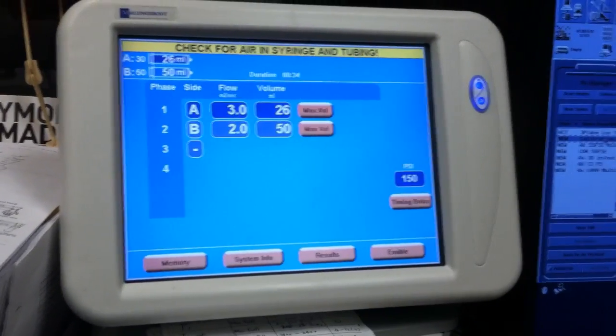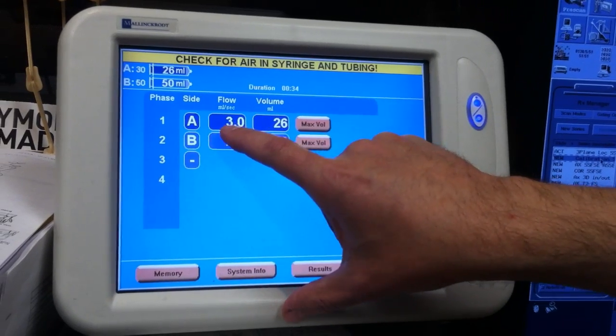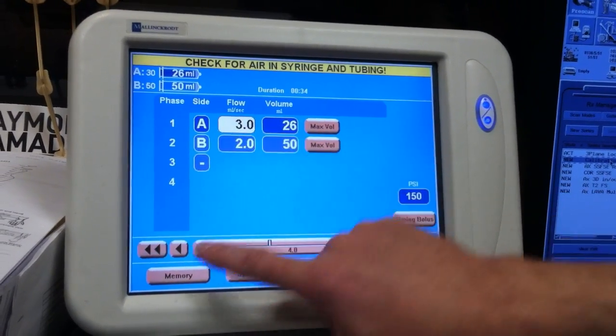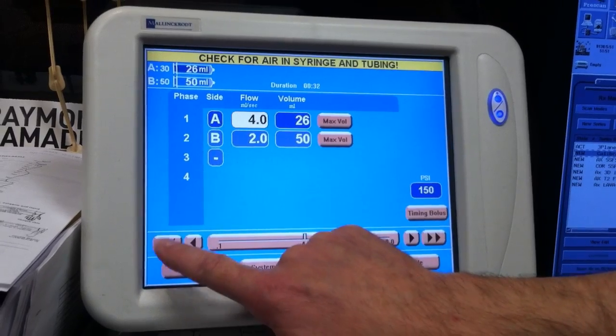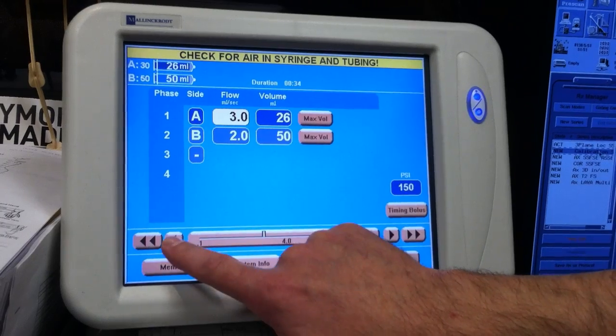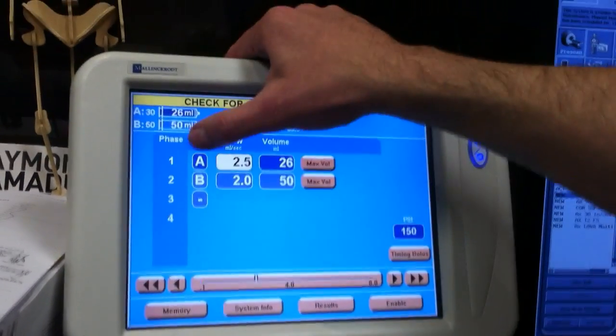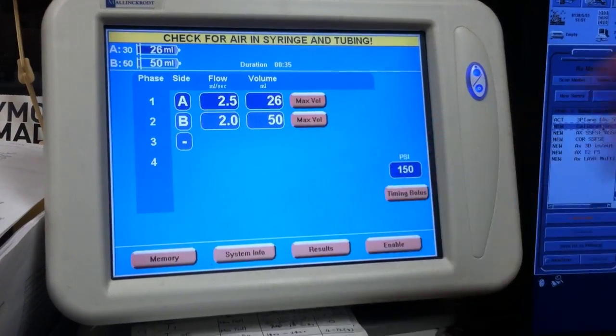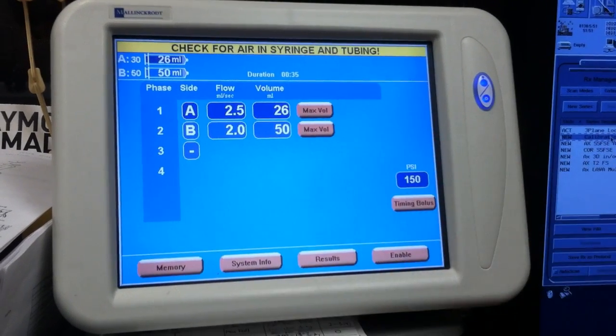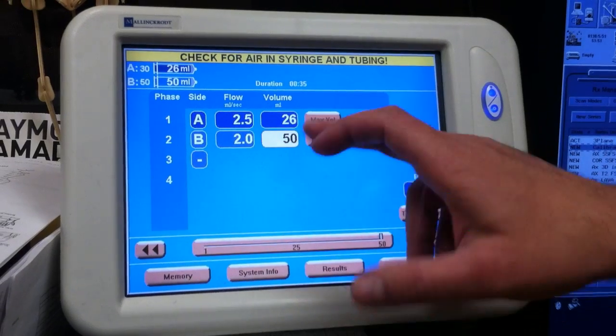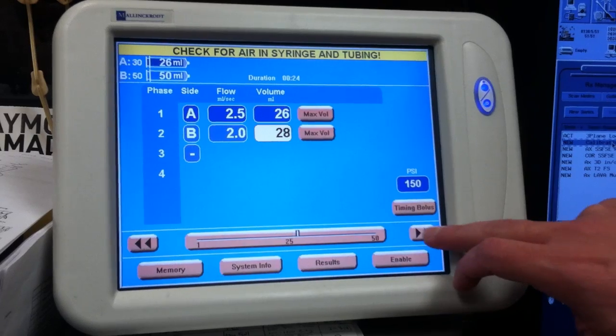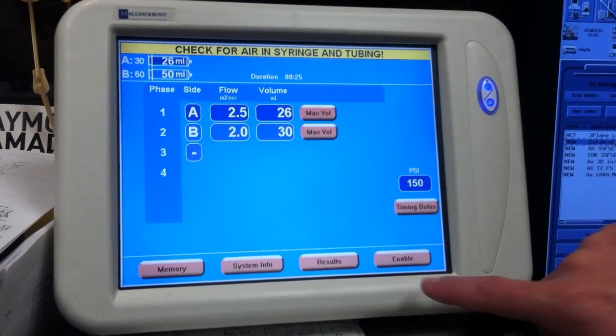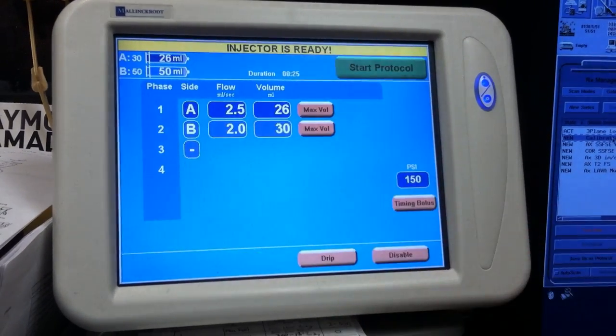Now, for a liver, we want to flow all of the contrast at once. We want to do it at a pretty high rate. In this case, it's three milliliters per second. We can change that here to whatever we want, but in this case, we want to do it about three. If the patient has weak veins, you can get it down to 2.5, but I wouldn't go any lower than that. Now, A is our contrast side. B is our saline side. Saline, it doesn't have to push so hard. It can be done at 2 or below. It just cleans the line and the vein out going to the heart and gives the patient a little extra hydration. And you only need about maybe 25 or 30 cc's of saline, not too much. And that's how you set up the power injector. Don't forget to enable it. And have we checked to get all the air out? Yes.